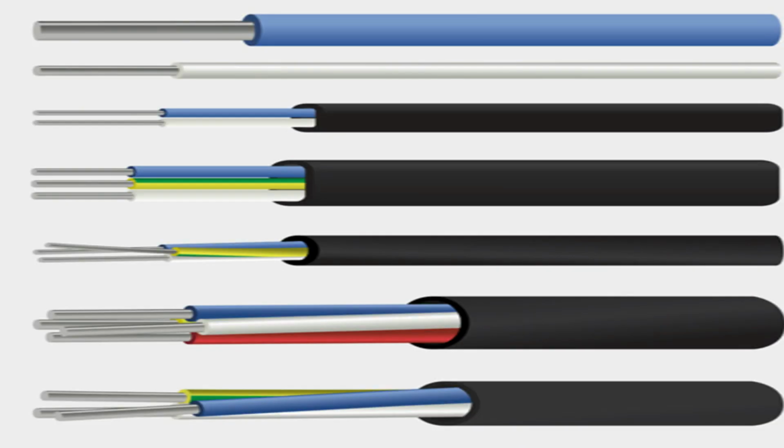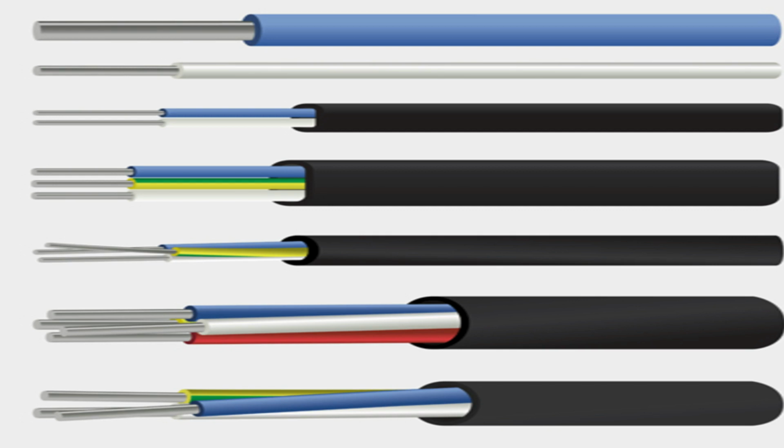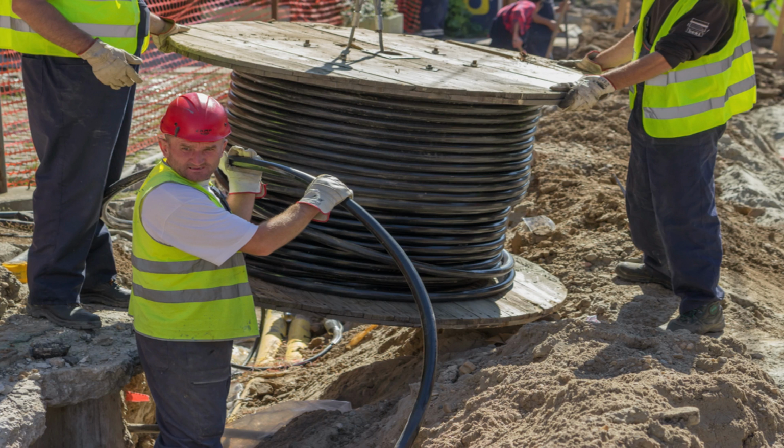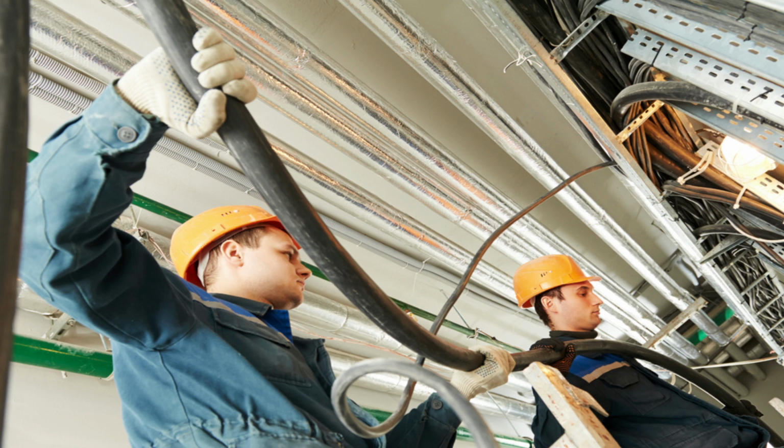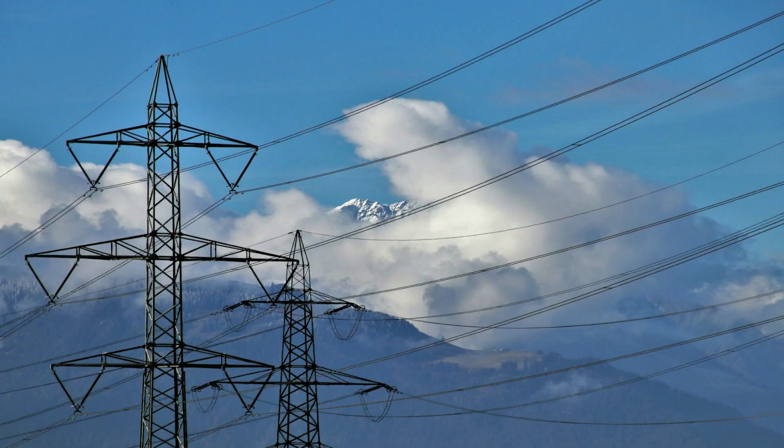Other than these two issues, aluminum cable is a successful alternative to copper cables, particularly in terms of its performance and pricing when proper techniques are used. Moreover, aluminum is 70% lighter than copper cable of the same amount. This makes their installation require less tensile force.